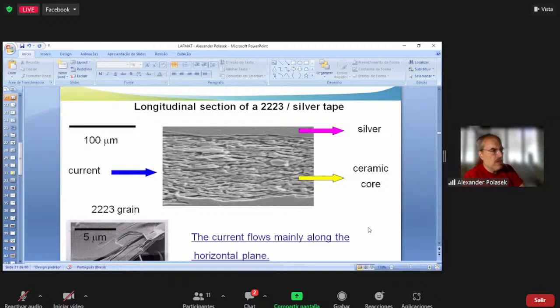Oh yeah, it's a good question. Normally they have to, a figure of merit is the compactness. For example, the idea is that typically one underground superconducting cable can transport the same current as 3 to 9 conventional copper cables, because one superconducting cable can carry 3 to 9 times higher currents than one conventional cable. It is a figure of merit, because if you don't have a much higher current density, it doesn't make sense.